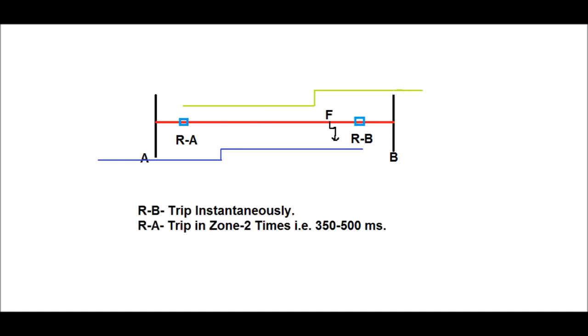Consider a fault occurring at a point F which lies 85% of the distance from relay A, and it lies in zone 1 of the relay at the B end. Relay B will trip instantaneously, but relay A trips in zone 2 time, that is, with a delay between 350 and 500 millisecond.